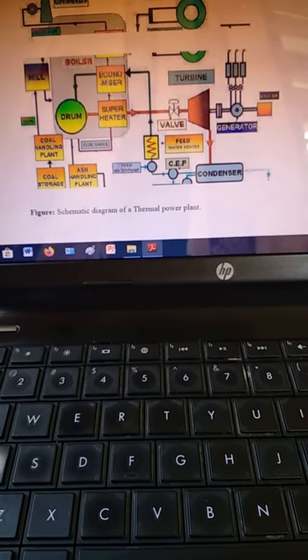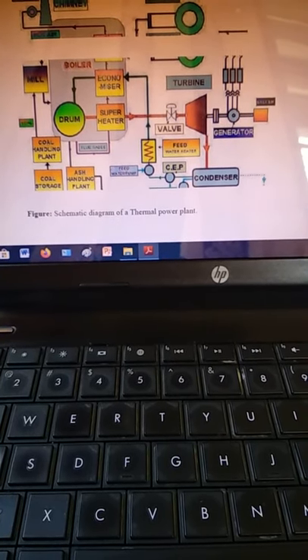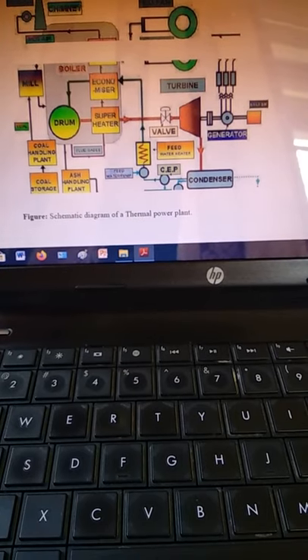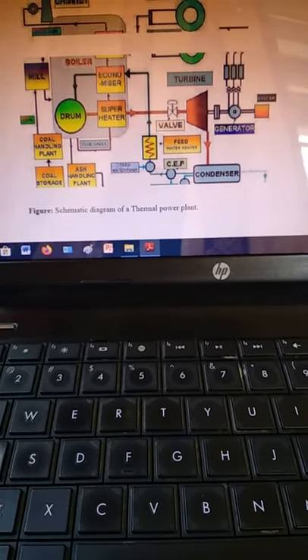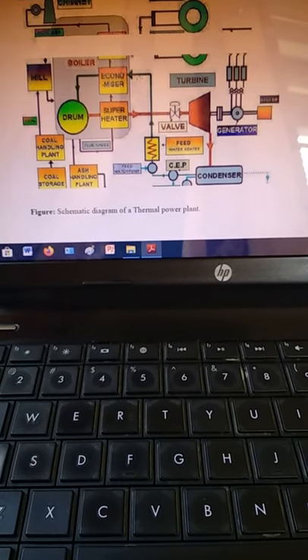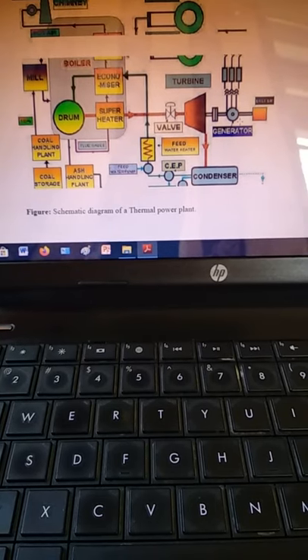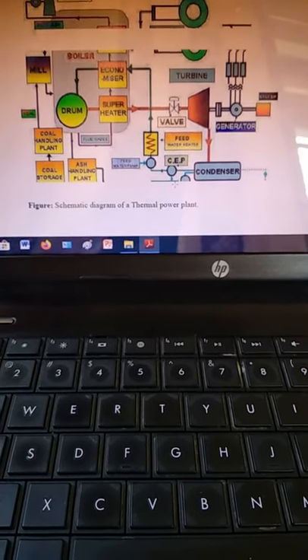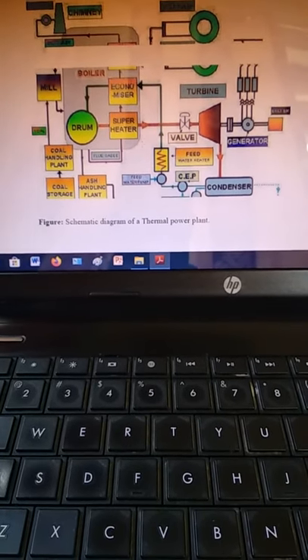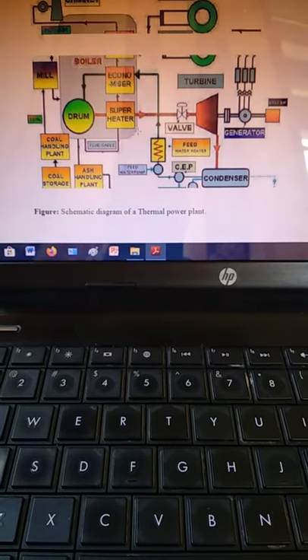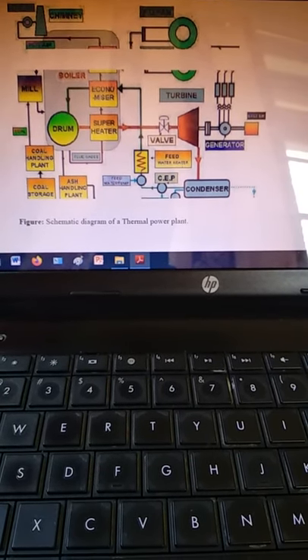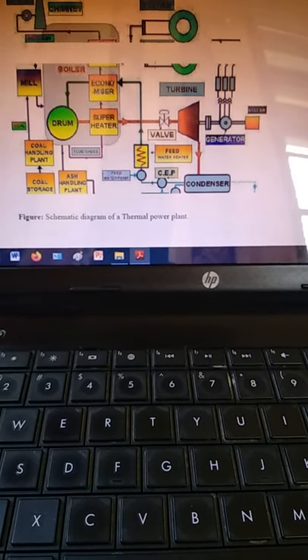There is also an ID fan and a superheater connected via a valve to the turbine. The steam coming out from the turbine goes to the condenser. After condensing, it goes to the condensate pump — also called the feed water pump — which lifts the liquid condensate back into the economizer. The turbine is coupled with the generator. These are additional parts beyond what is needed for the Rankine cycle.